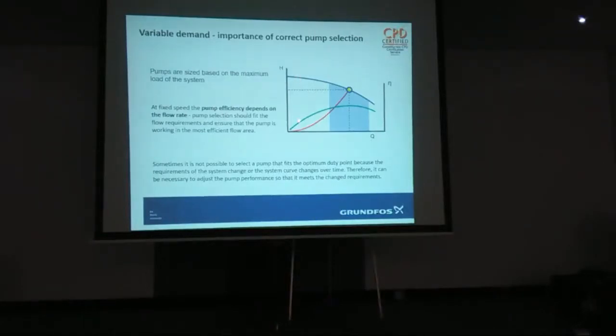If you're in this area, you're down the efficiency side. You're still using relatively low power, but you haven't got as much control. And the other thing to bear in mind is something I'll come on to later on. You can't always select a pump to work in that area, because you might have half a litre a second at 250 kPa. And the 32 mil pump, at that kind of duty, will do something in the 3.5 litres a second maybe. So if you've only got half a litre a second, you're going to get a duty up there somewhere. So your efficiency percentage goes out the window.